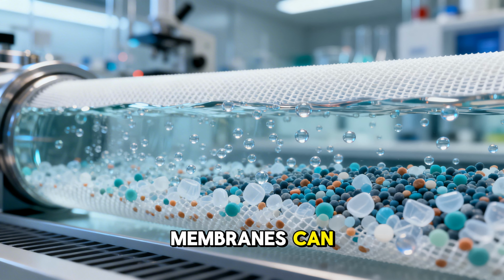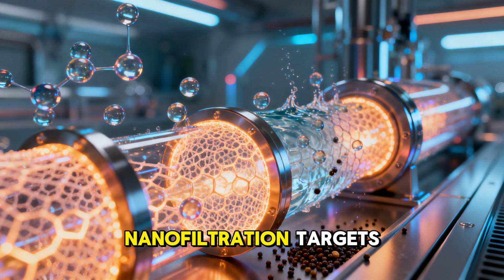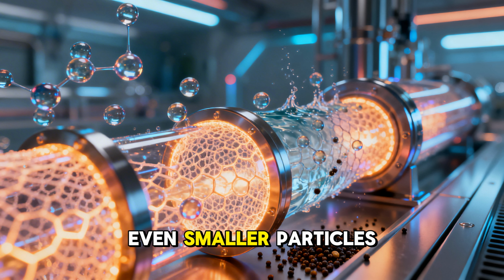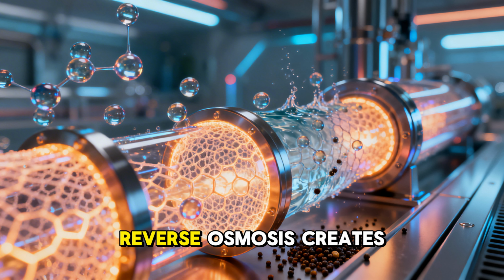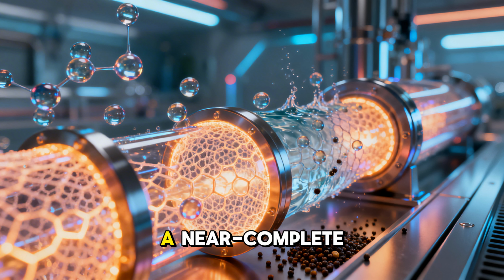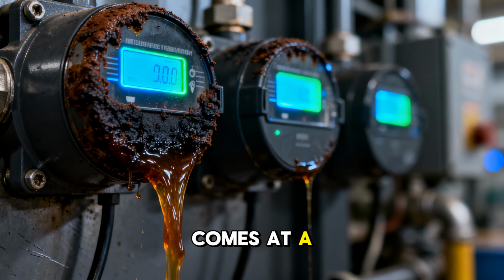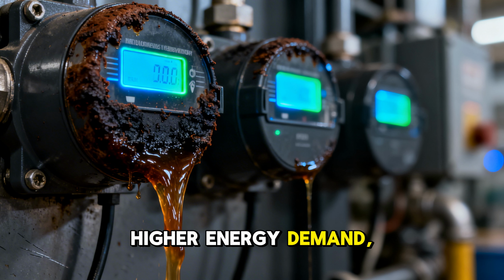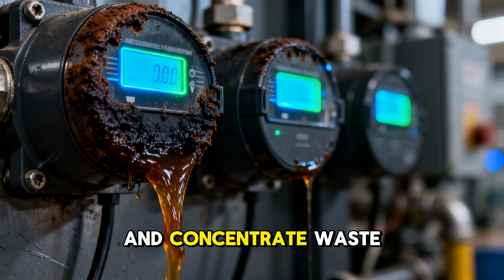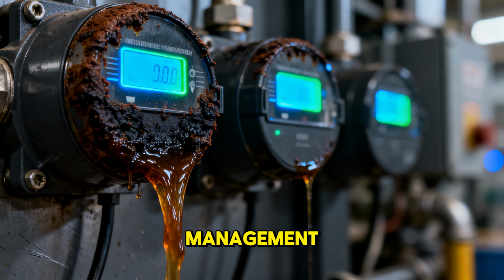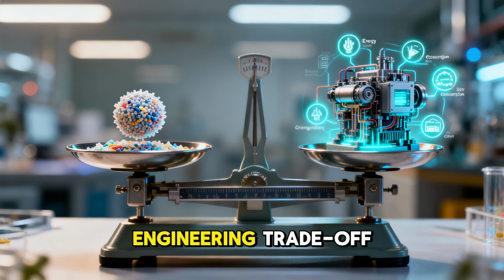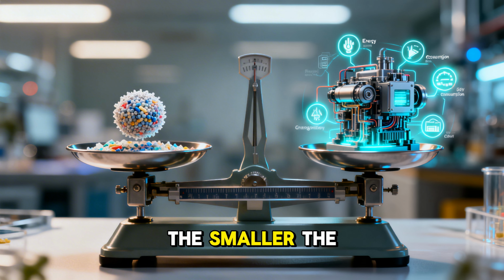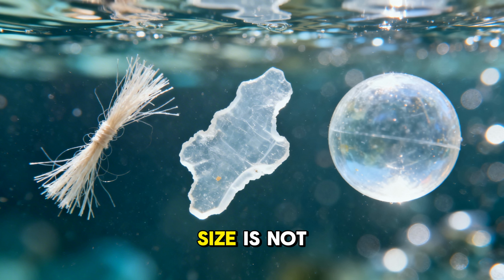Ultrafiltration membranes can remove most microplastics, and nanofiltration targets even smaller particles. Reverse osmosis creates a near-complete physical barrier, but this performance comes at a cost: higher energy demand, membrane fouling, and concentrate waste management. This is the fundamental engineering trade-off. The smaller the particle you want to remove, the more complex and energy-intensive the system becomes.